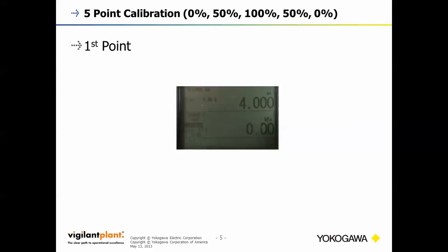So typically, in calibrating a pressure transmitter, you do a 5-point calibration, so three up and two down, or you might even do a 9-point calibration, 5 up and 4 down. But we're going to do a 5-point calibration today, so 0%, 50%, 100%, and back down to 50 and 0. You go up and then down just to make sure there's no inherent hysteresis or play, so that when you come back down, the 0 doesn't drift.